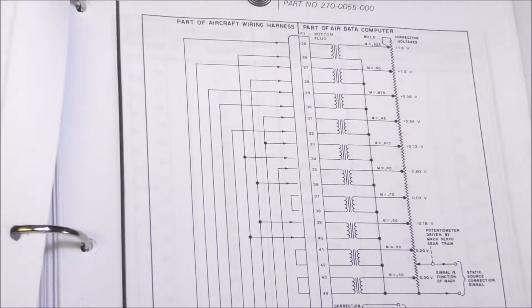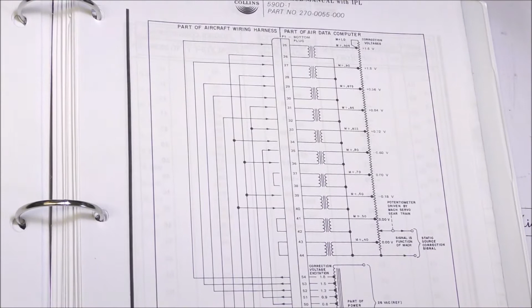So this is the SSEC correction, called the static source error correction. This is the potentiometer with different taps, which is linked to the Mach servo control. Depending on the Mach number, the wiper can change from this position at Mach 0 to Mach 1 here. This signal, an AC signal, is fed to the input of the servo control of the altitude. The terminals of the connector are available on the rear of this instrument.